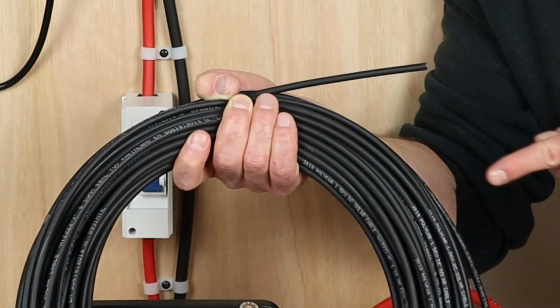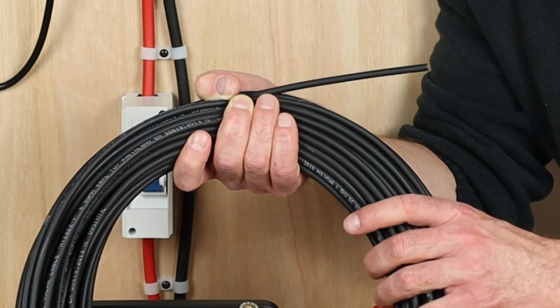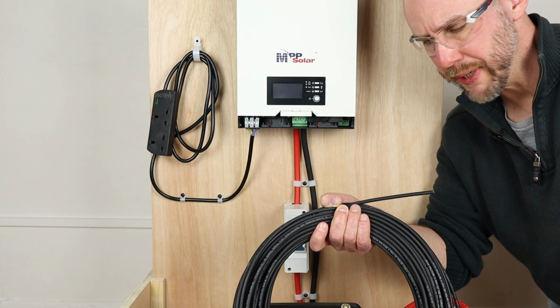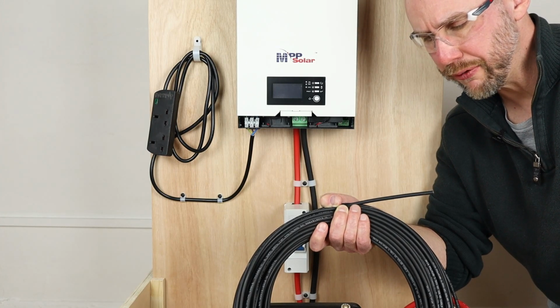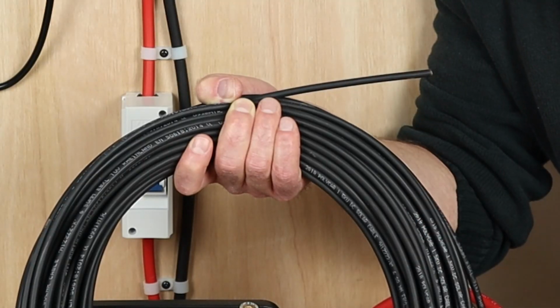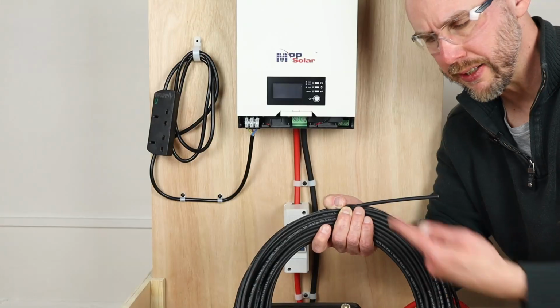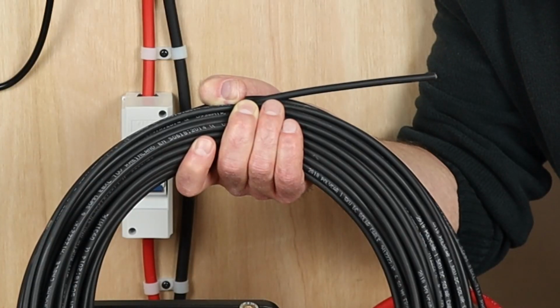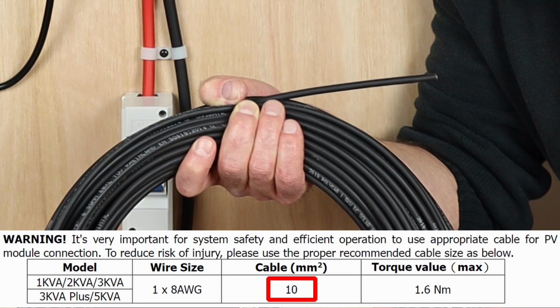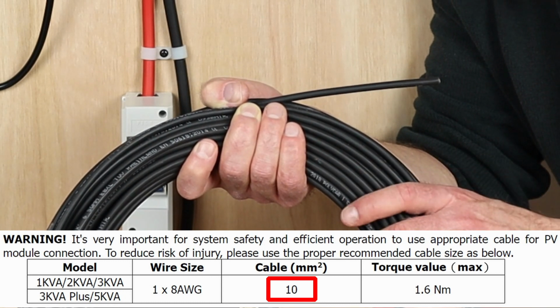I'm going to use some of this cable for my setup, which is solar cable, 6mm squared and rated up to 1.5 kilovolts. This is way over what I need for my 400 watt panel array to connect to this unit. The manual actually recommends a wire size of 10mm squared, but for my particular setup, this should be more than adequate.